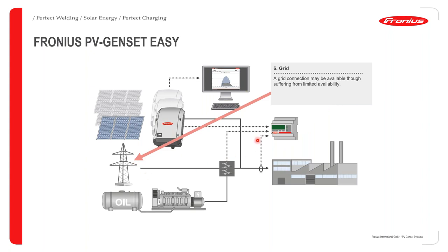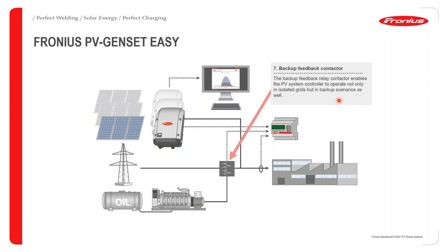In a grid backup scenario, the grid may be available but suffering from limited availability. The ATS — automatic transfer switch — is critical in this scenario. It uses a feedback contact relay to tell the PV system controller whether the grid or the generator is currently operating, so the controller knows whether to limit PV power or to apply the generator minimum load rules.